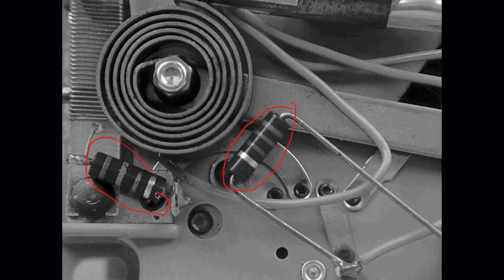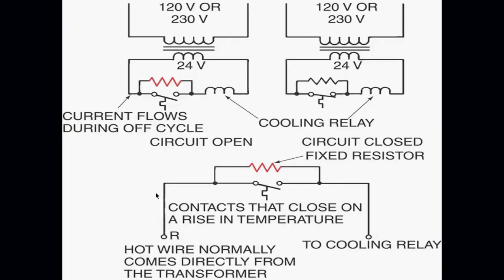So rather than have the house get to 75 degrees and the cooling system have to keep up, it's going to close the thermostat slightly before. It might close that thermostat when the temperature gets to 74.5 degrees. So it's sort of faking out the thermostat and saying the room temperature is actually half a degree warmer than it actually is.